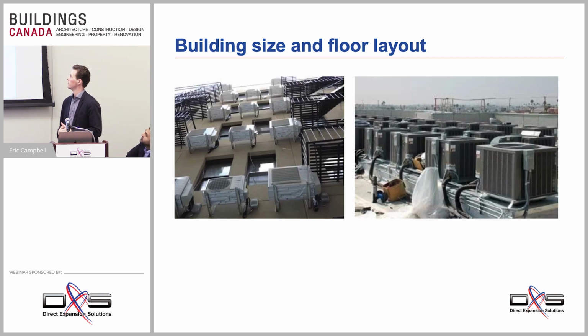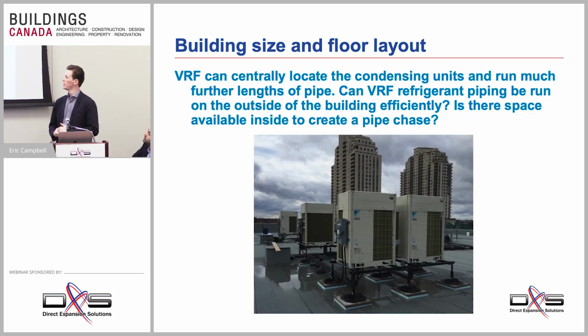There are ways to get around that. You can find spaces mounted on the outside of buildings, or you can take up a lot of your roof space in some cases with these condenser units, but again, we don't always have the line lengths to do that. If you've got a 10-story building, you can't put all the condenser units on the roof and serve those lowest floors with the decentralized system. We can, however, with a VRF solution. Here, there's much more flexibility in terms of piping lengths. We can run hundreds of feet between the outdoor unit and the indoor unit. And then we can take advantage of still using this air source heat pump technology, even for those larger, like 20-story buildings and above.